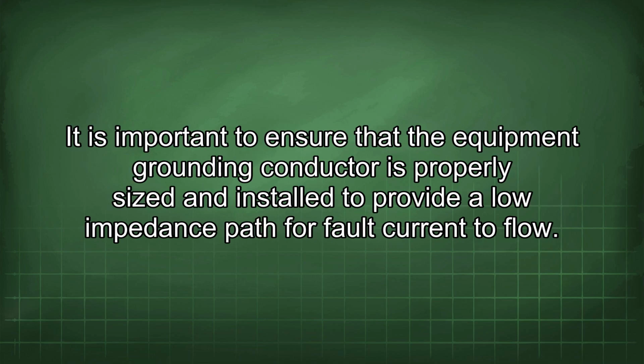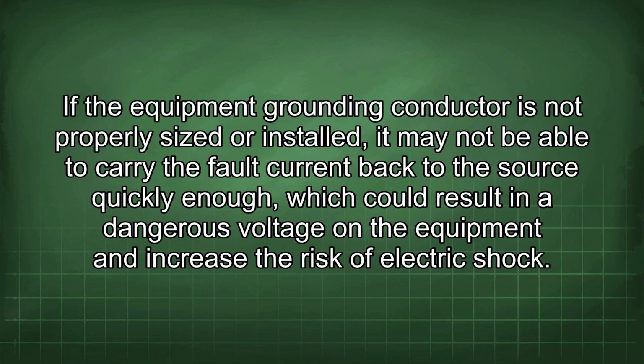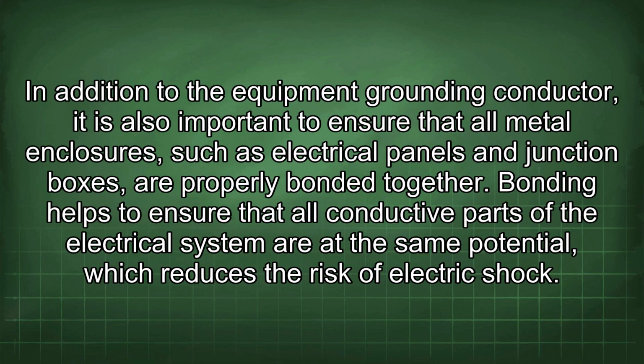It is important to ensure that the equipment grounding conductor is properly sized and installed to provide a low impedance path for fault current to flow. If the equipment grounding conductor is not properly sized or installed, it may not be able to carry the fault current back to the source quickly enough, which could result in a dangerous voltage on the equipment and increase the risk of electric shock.